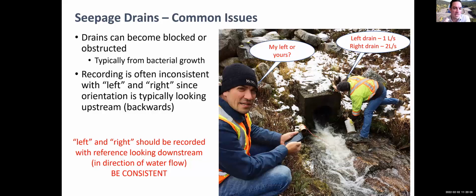Other potential common issues: Dwayne talked about bacterial growth. You can see this orangey sludge in those drains. In this case, I wouldn't clean them and wait. It kind of depends, because the water will be flowing over some of this sludge. So you could measure the flow coming out of them and then clean the drains after, whatever seems to be working in your particular case.